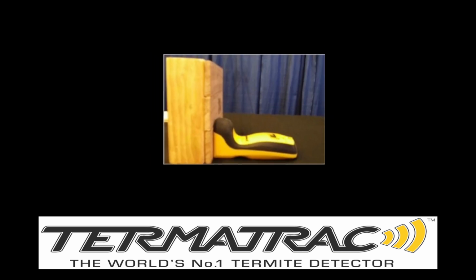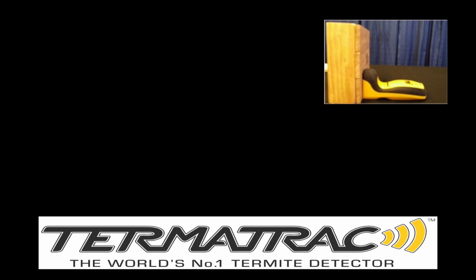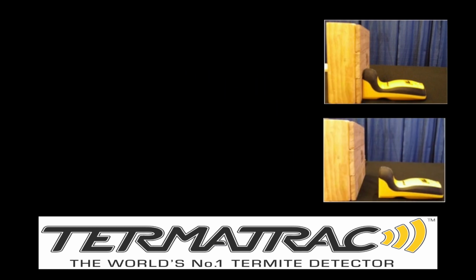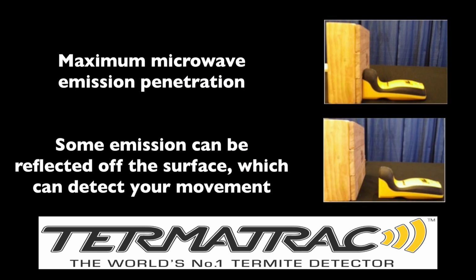When using the T3i unit, the optimum positioning is flush against the surface you are trying to test. This reduces any of the microwave reflection coming off the surface, and the higher the gloss surface, the more reflection that can happen. To avoid this, try and keep it flush where possible.